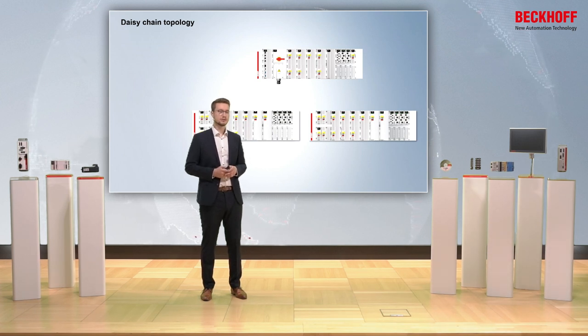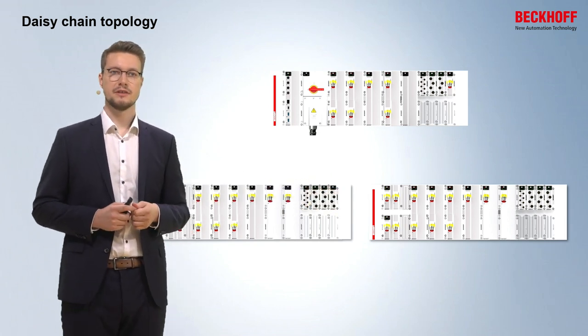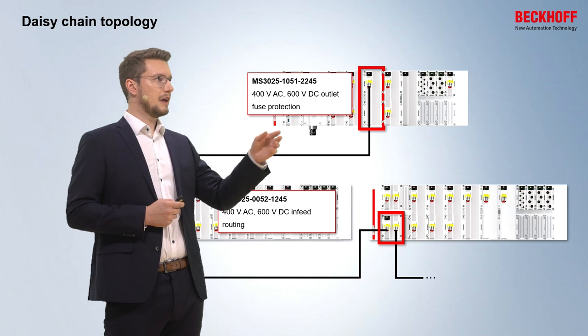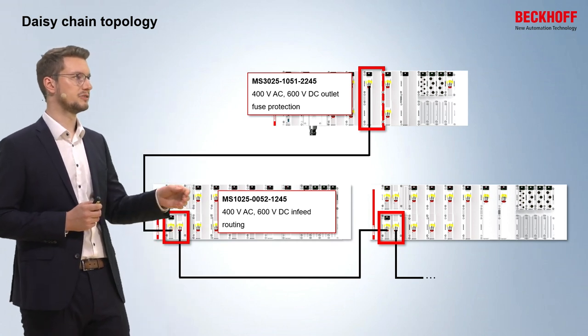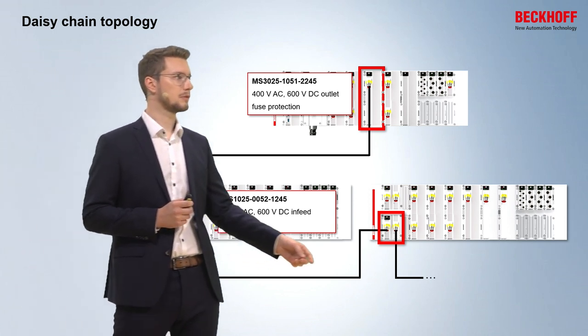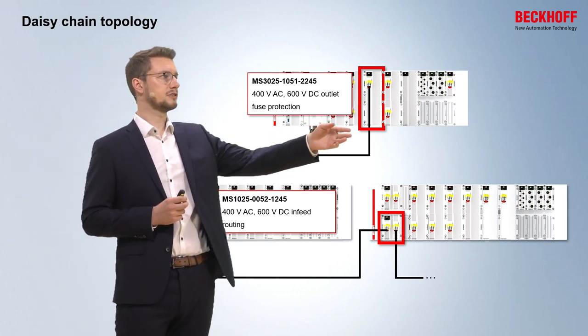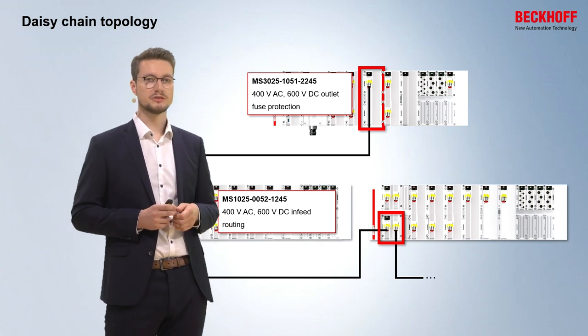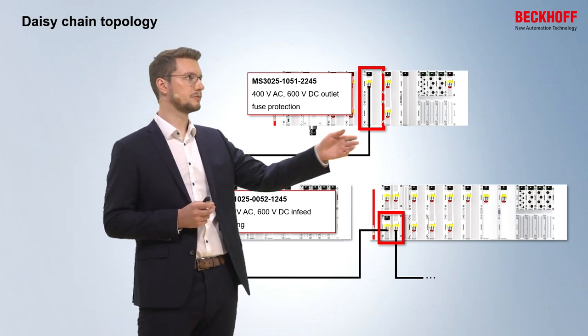In this topology example, we want to build up a daisy chain. We have three MS system stations: the upper one is the main station and the two lower ones are subsystems. We can have an output of 400V and 600V in the main station to provide voltages for the two subsystems — the first subsystem has an output and connects the second subsystem with the voltages. Only the first output in the main station has a fuse protection built in, so if there is an error in the cable between the two subsystems, both subsystems are shut down since there is only one fuse in the main station.